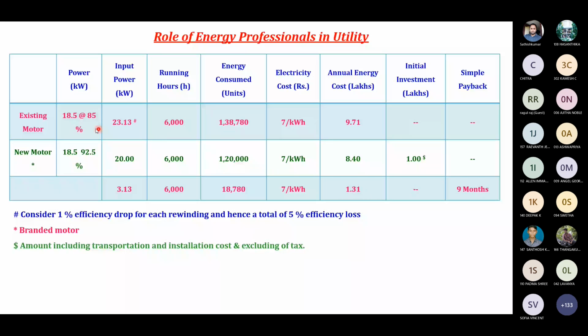Same motor, if I replace it with the new motor, it is going to be 18.5 kilowatt divided by 0.925. Now it takes only 20 kilowatt. At full load condition, the old motor will take 23.13, but the new motor will take only 20 kilowatt. So the difference between these two is 3.13 kilowatt multiplied by 6,000 hours. Power multiplied by hours equals energy. So if you replace the old motor with the new motor, yearly you can save nearly 19,000 units. 19,000 units is the saving.